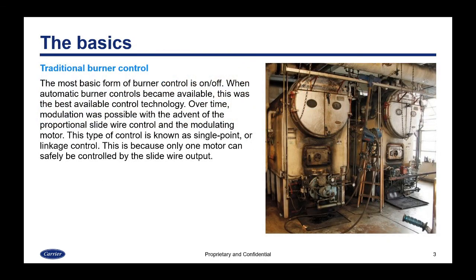So with traditional burner control, the most basic form was on-off control. When automatic burner controls became available, that was the best available control technology. And over time, modulation did become possible with the advent of the proportional slide wire control and the modulating motor. And that type of control, which can still be seen today, is known as single point or linkage control. And it's called that because only one motor can safely be controlled by the slide wire.